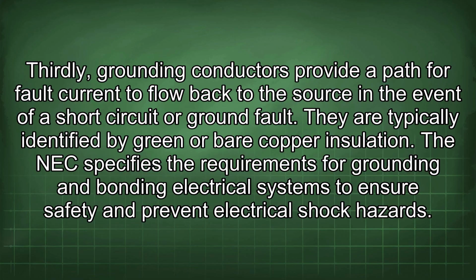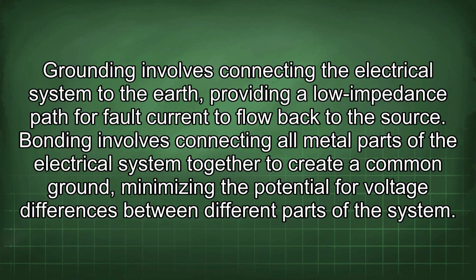The NEC specifies the requirements for grounding and bonding electrical systems to ensure safety and prevent electrical shock hazards. Grounding involves connecting the electrical system to the earth, providing a low impedance path for fault current to flow back to the source. Bonding involves connecting all metal parts of the electrical system together to create a common ground, minimizing the potential for voltage differences between different parts of the system.